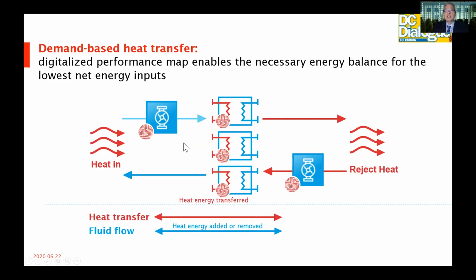We can also take this concept to the next level, an energy transfer station, where we can create that same digital fingerprint or equipment performance model of the heat transfer surface area. So we're able to monitor the heat transfer coefficient for the whole device. We're able to observe the changes over time if one side starts to get contaminated. We're able to track the amount of energy to move the water through the devices by combining it with intelligent flow management systems. And we're able to create a digital fingerprint or performance map for that whole energy transfer station.